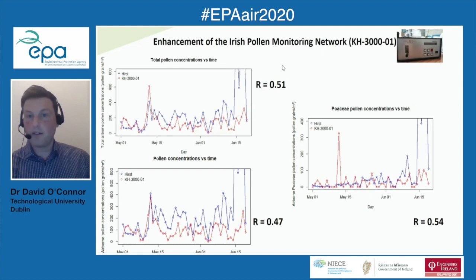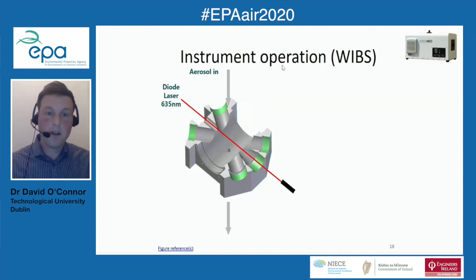Moving on to the WIBS Neo, I just want to give a bit more of an overview of how this instrument works, because it's a lot more dedicated towards bioaerosols than just using forward and side scatter like the Japanese pollen counter. Essentially, your ambient air gets sucked in and gets hit by a diode laser at 635 nanometers. This gives us size and shape information, again using side and forward scatter and using Mie theory to determine the size of the particle.